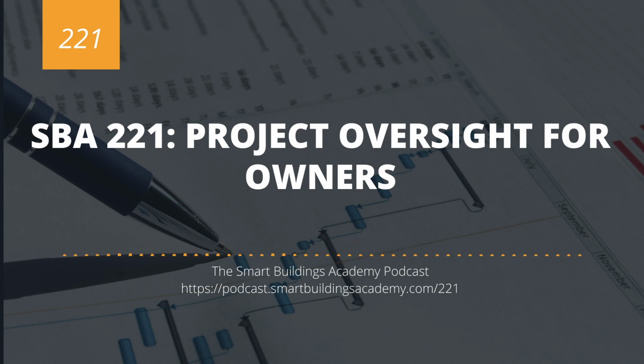Standards should communicate not only submittal development, not only sequencing, but also naming, graphics, O&Ms, training, your actual as-builts, all of these processes that should be dictated. You can get as granular as down to what wire types you use and what panels you use. I will tell you, for some of our customers who are critical facilities, it makes complete sense to have a wiring standard so that literally their people can go and look in a panel and say, oh, orange wire means this, red wire means that, blue wire means this. And by looking at that, they can instantly tell what's going on.